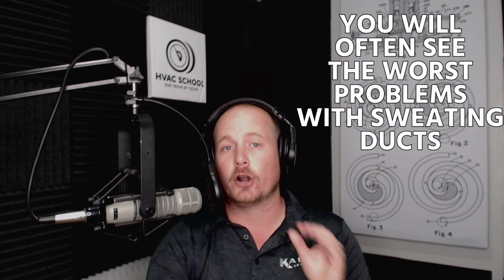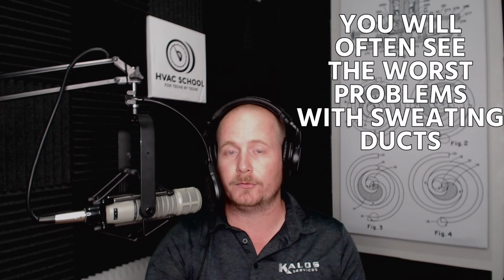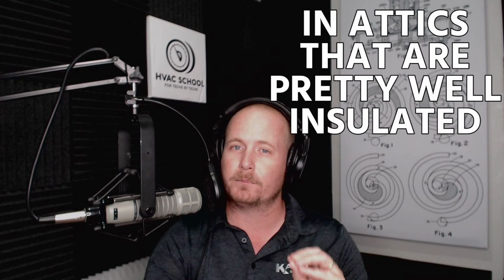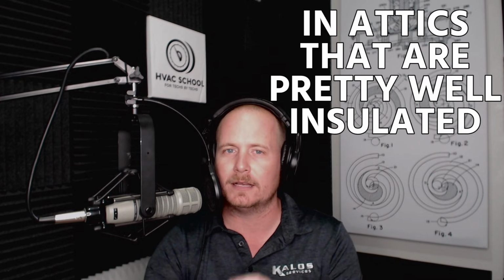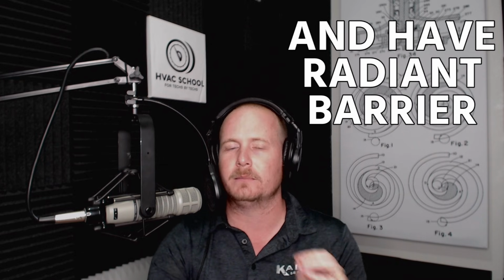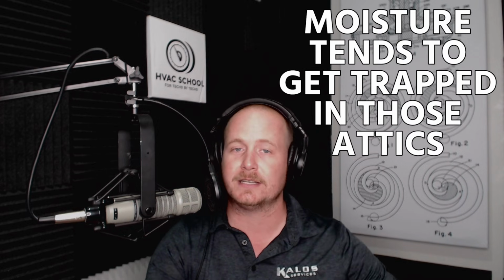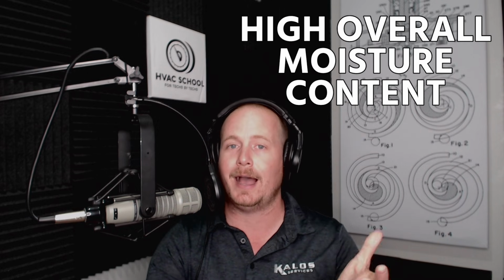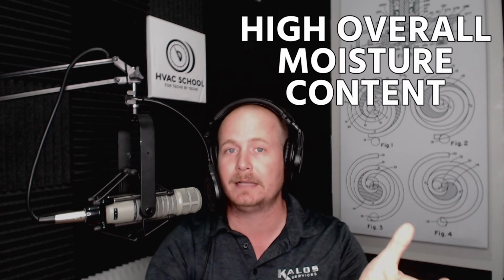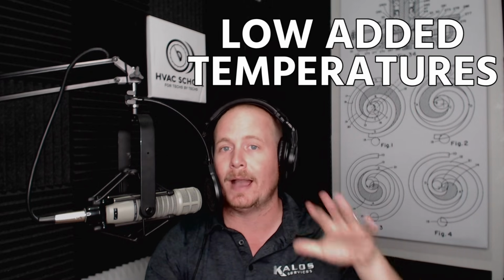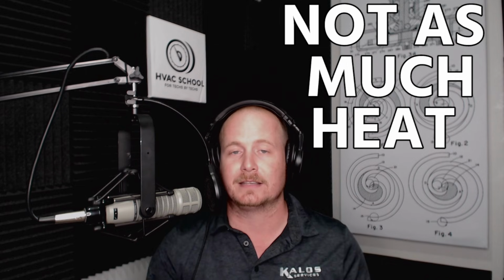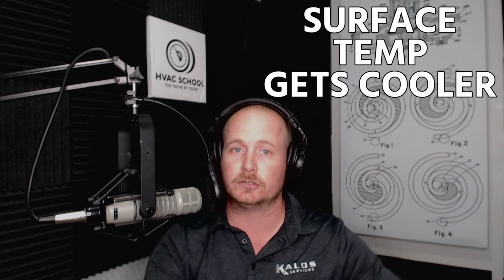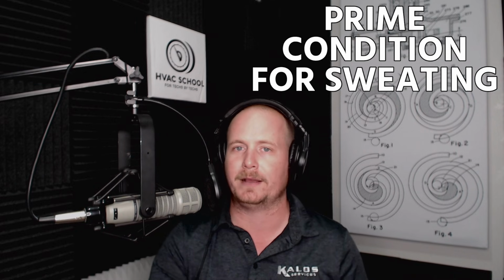Quick pro tip here, you're often going to see the worst problems with sweating ducts in attics that are pretty well sealed, pretty well insulated, and have some sort of radiant barrier. And the reason is because moisture tends to get trapped in those attics, so you have high overall moisture content in grains, high relative humidities, and low attic temperatures. When you have that low attic temperature, now you don't have as much heat that's conducting into the duct itself, and so that surface temperature gets cooler. So now you have that kind of prime condition for sweating on the surface of the duct.